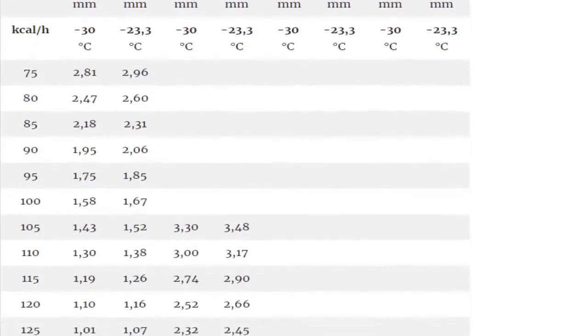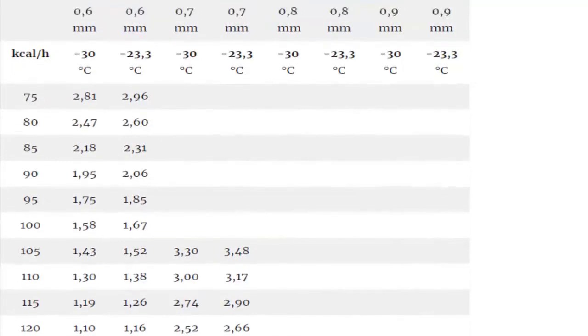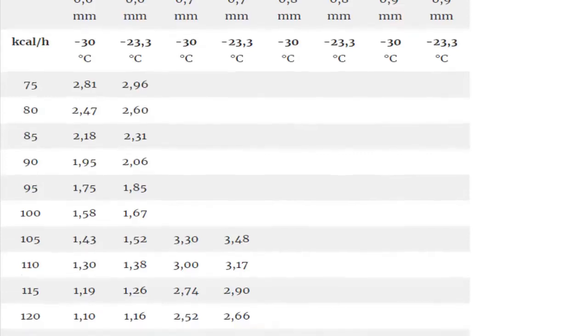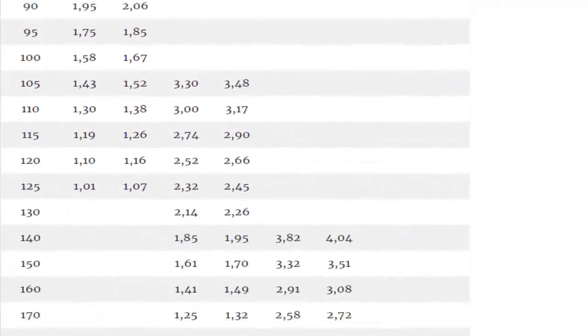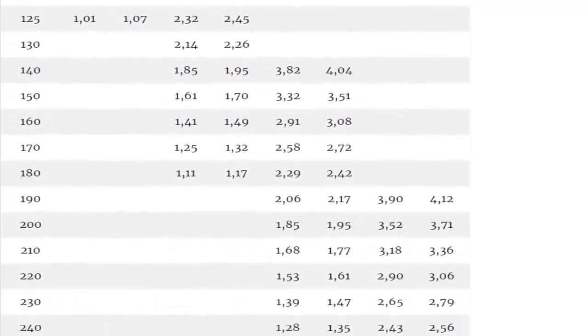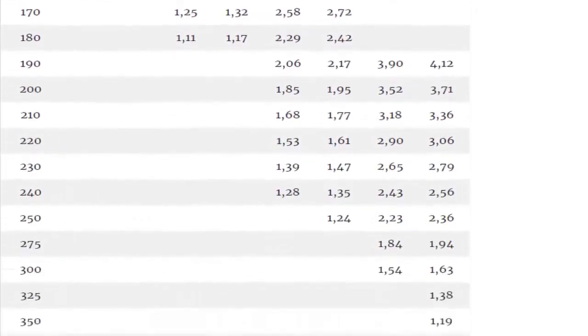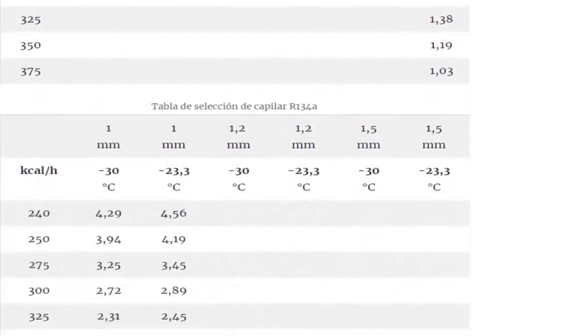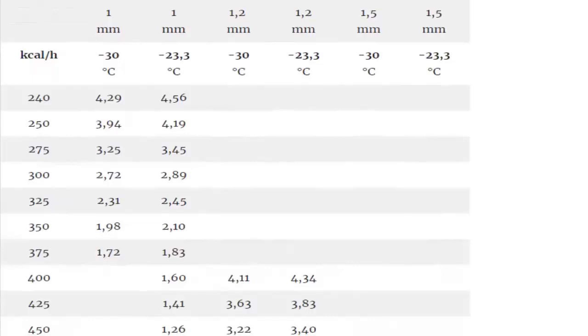1. Capillary tubes depend on both their length and their diameter to determine their total restriction. 2. The mission of the capillary is to delay the passage of refrigerant that reaches the evaporator to maintain the low pressure that causes the suction of the compressor. 3. The two variables to take into account for capillary selection are mainly the evaporator temperature and the cooling capacity of the compressor. 4. We must not confuse the cooling capacity with the electrical power of the compressor, the latter normally measured in HP.